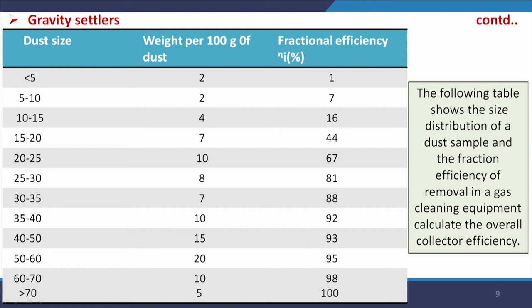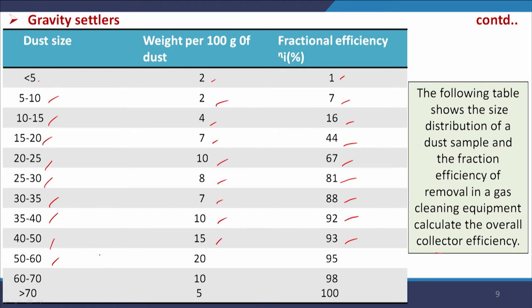A numerical problem: the following table shows the size distribution of a dust sample and the fractional efficiency of removal in a gas cleaning equipment; calculate the overall collector efficiency. The table gives: dust size <5 μm: 2g, efficiency 1%; 5–10: 2g, 7%; 10–15: 4g, 16%; 15–20: 7g, 44%; 20–25: 10g, 67%; 25–30: 8g, 81%; 30–35: 7g, 88%; 35–40: 10g, 92%; 40–50: 15g, 93%; 50–60: 20g, 95%; 60-70: 10g, 98%; >70: 5g, 100%.